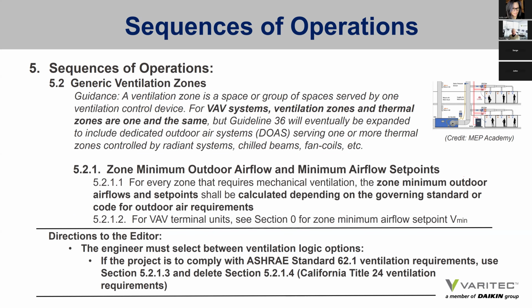A ventilation zone is a space or group of spaces served by one ventilation control device. For VAV systems, ventilation zones and thermal zones are one and the same. That will change with 100% outside air systems, but we're still waiting for language on that. There's language for zone minimum outdoor airflow rates and minimum airflow set points. For every zone that requires mechanical ventilation, the zone minimum outdoor airflows and set points shall be calculated depending on the governing standard and code authority.